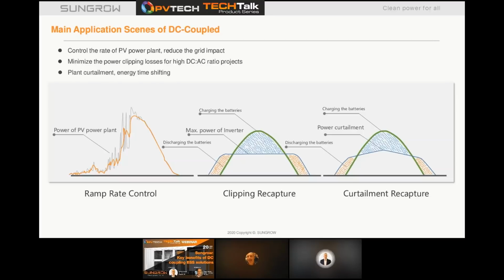The center graphic illustrates the power curve with larger DC-AC ratios being designed due to the lower cost of modules. This is good in winter, but what happens in summer? The inverter is only able to convert a maximum amount of energy, so surplus energy is lost. Clipping recapture will allow you to store this surplus energy for use either before sunrise or after the sun sets.